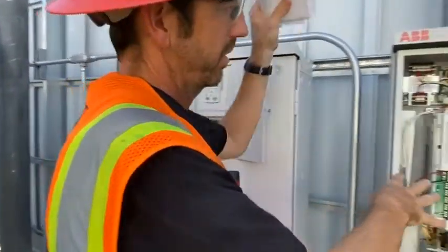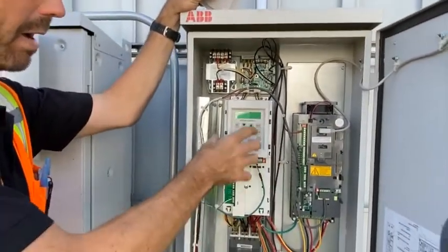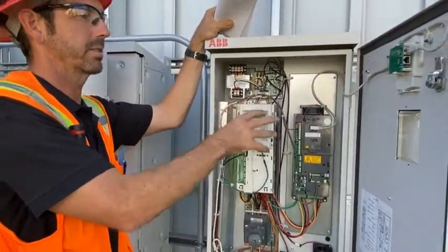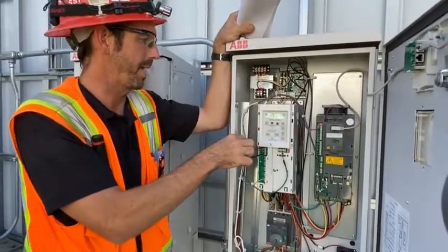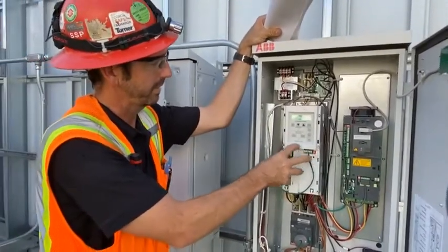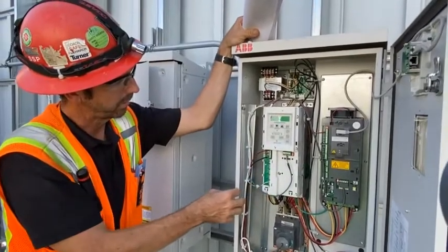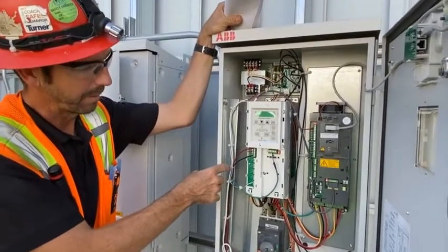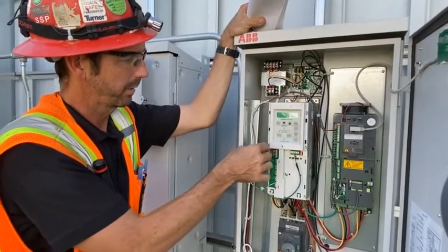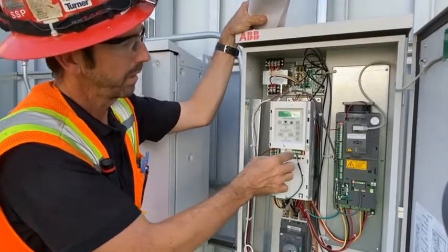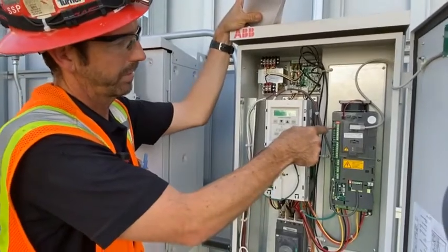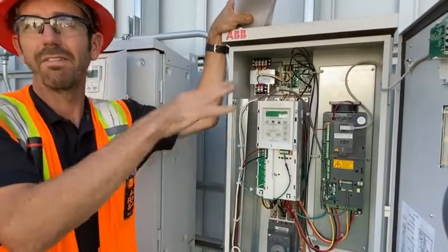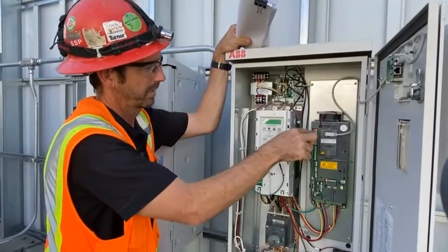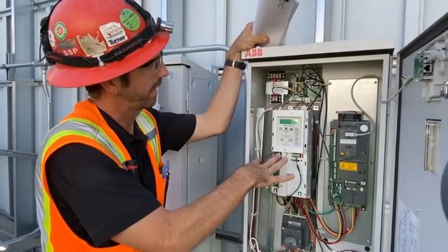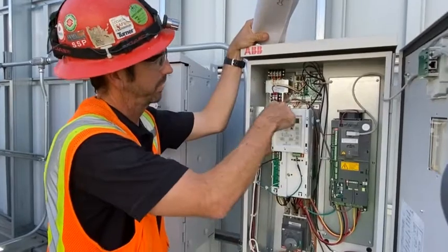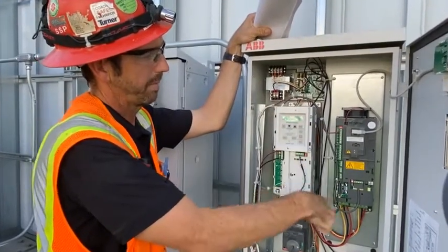Back over here, just so you can see the internals, all the controls are done on the bypass, even though we're not using it. It's configured for the Eclipse bypass, so the main brain of this apparatus is in the bypass. The start/stop and all the enable from BMS is terminated on the bypass board. Just the analog input signal is over here. That's the speed reference signal on how fast the drive should be running. That's the only thing that gets landed on a drive with the Eclipse bypass. Everything else runs through this communication cable, which is Modbus, from the Eclipse bypass to the drive.